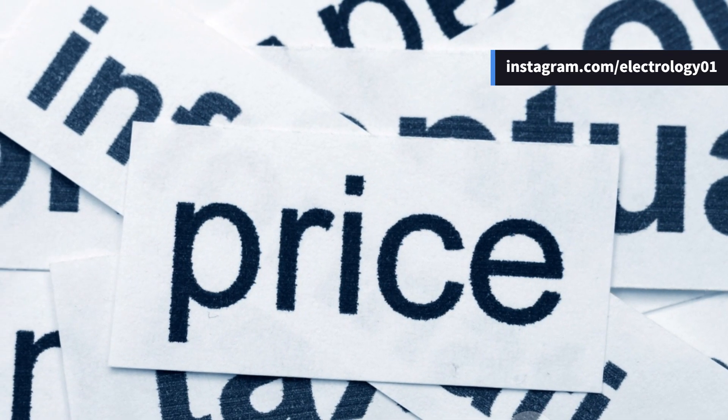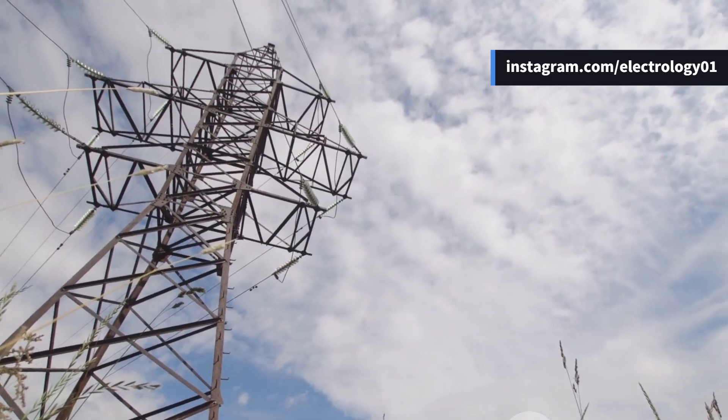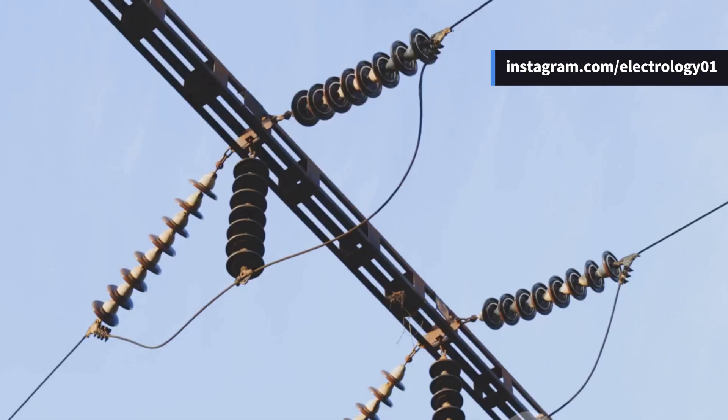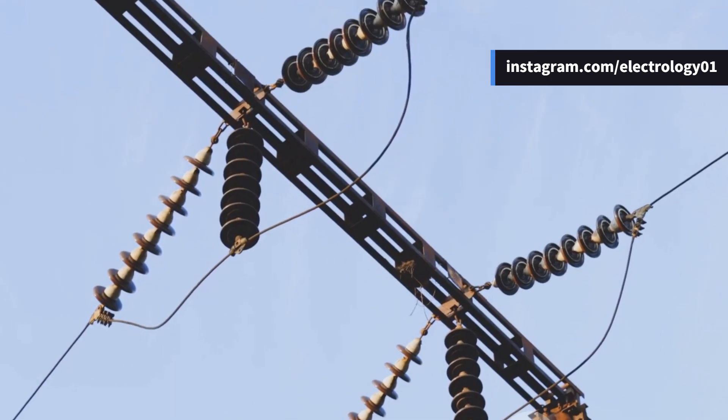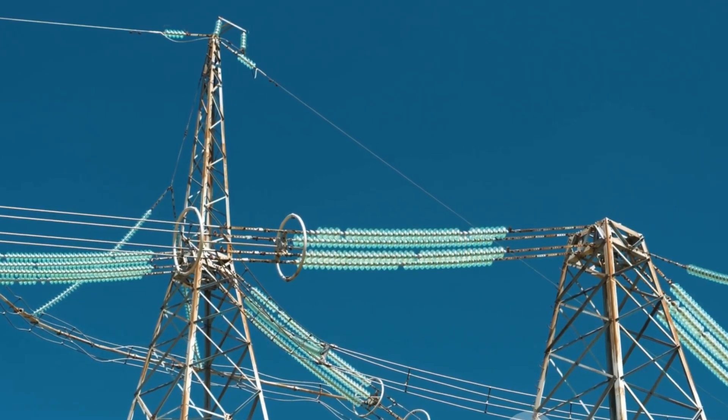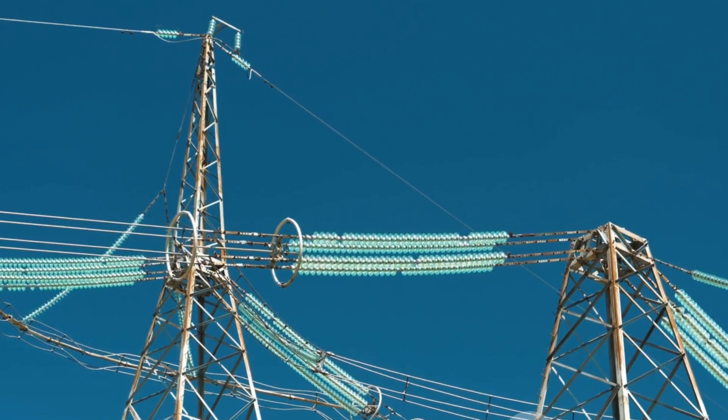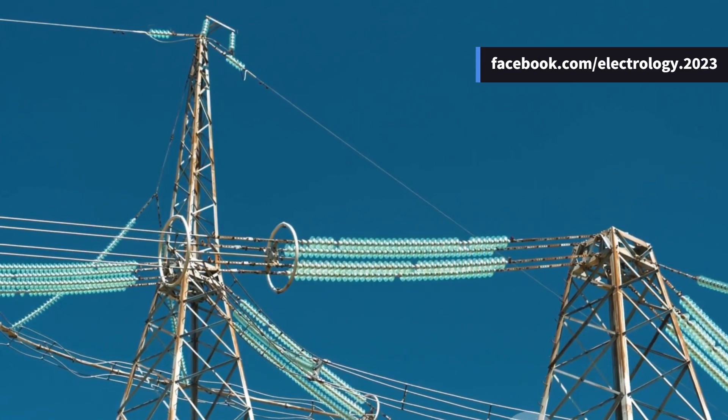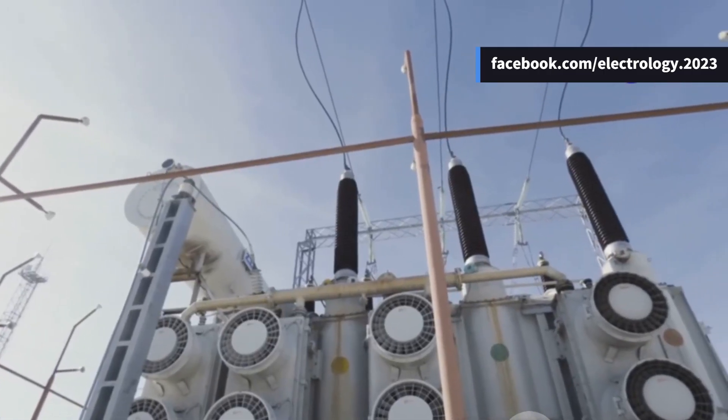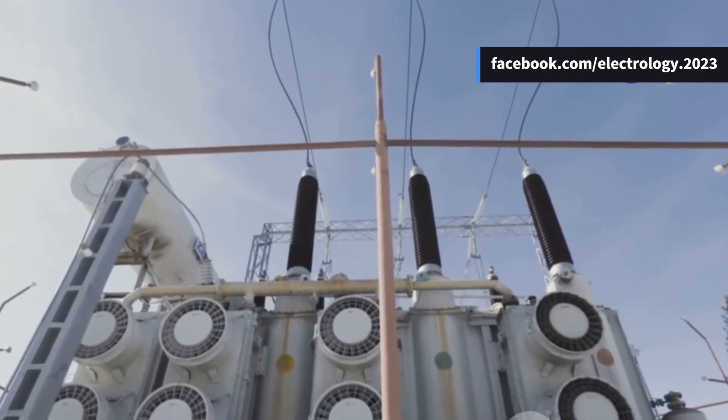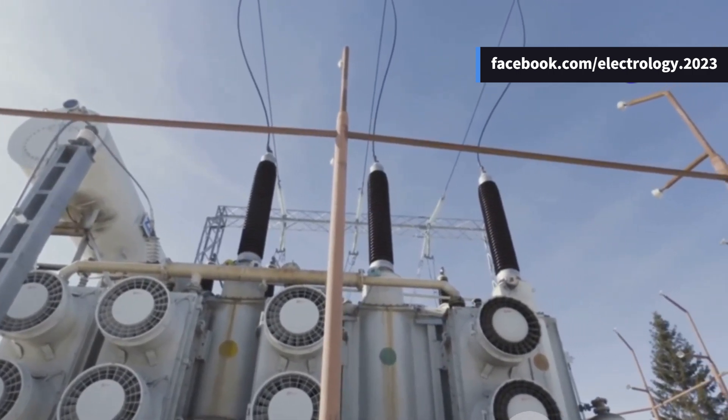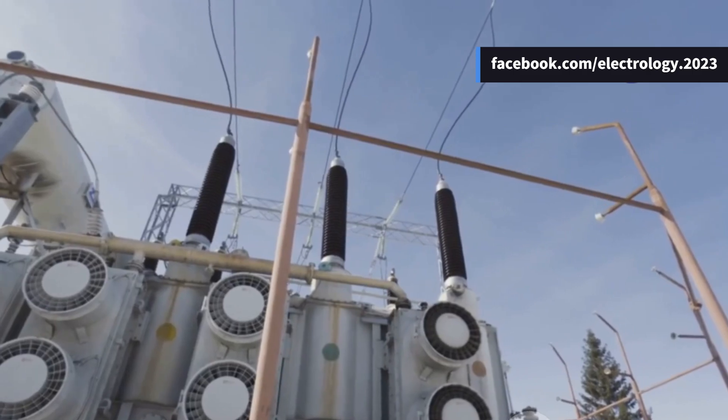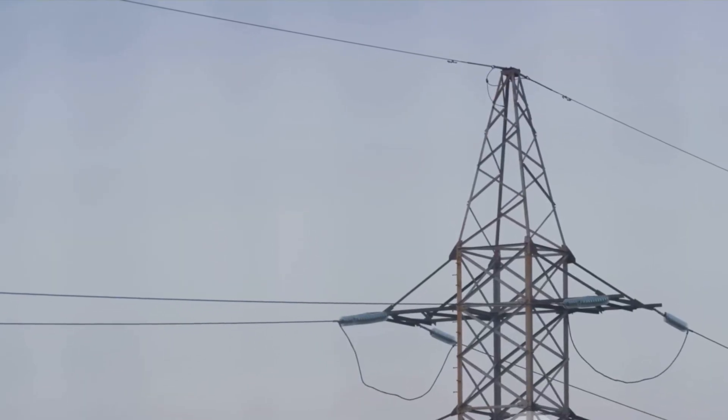Now everything has a price, and high voltage transmission is no exception. First, the cost of insulation increases. The conductors must be spaced further apart and better insulators must be used to handle the higher voltage stress. Second, the cost of terminal equipment increases, including transformers, switchgear, surge arrestors, and more. These costs can sometimes outweigh the savings in conductor material, especially at extremely high voltages.